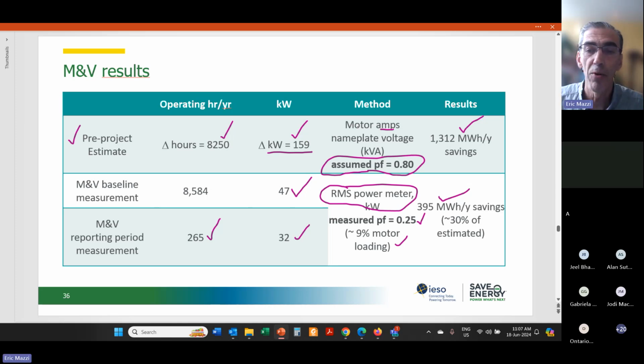excuse me, a high proportion of those motor amps measured in the baseline were magnetizing current. It was not for real power. If that doesn't make sense to you, you'd have to do a little review and background on electrical engineering and electric power systems, and that you have magnetizing current, magnetizing power, you have real power, and the energy savings is based on real power savings.